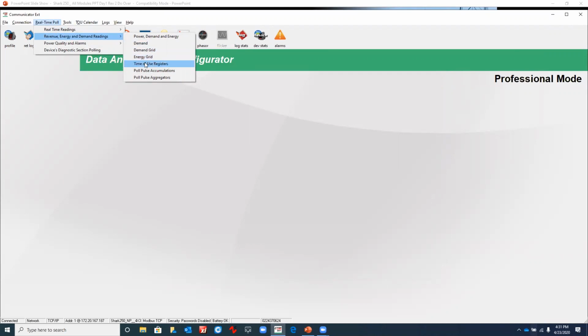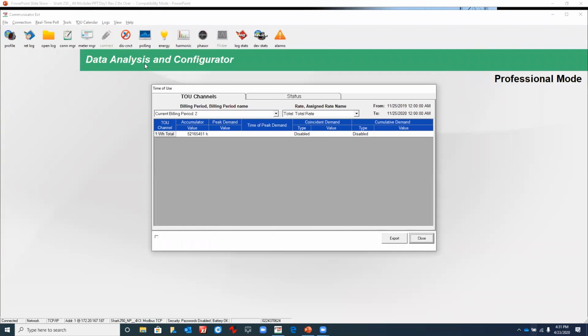So time of use is where we are now. Time of use gives us the ability to set up the meter for time of use, or we call it time of demand, or TOD, or there are lots of different names or terminology that people use. Basically these are primarily set up for customers that are signed up for this program, usually with a utility, where they would get a certain rate based on the time of their consumption. And so this allows the meter to capture that information.